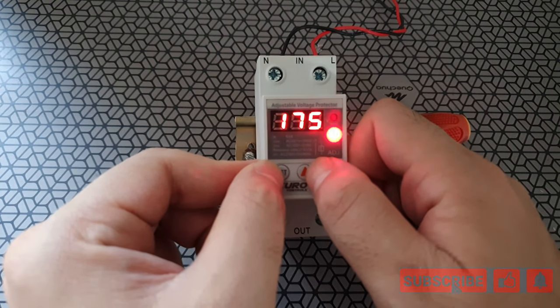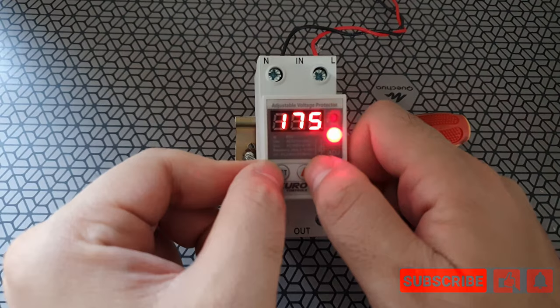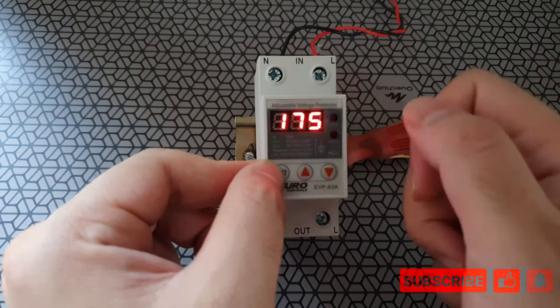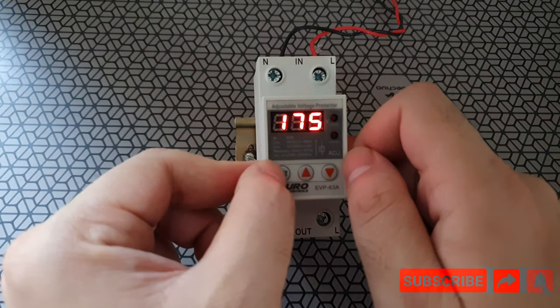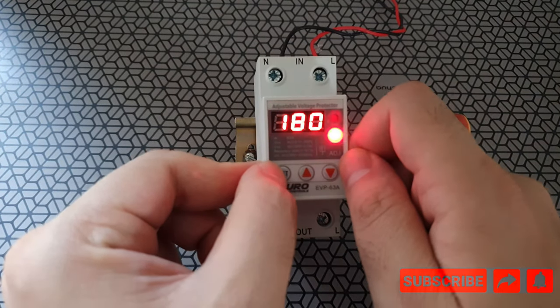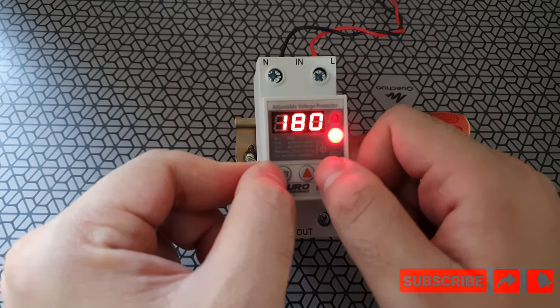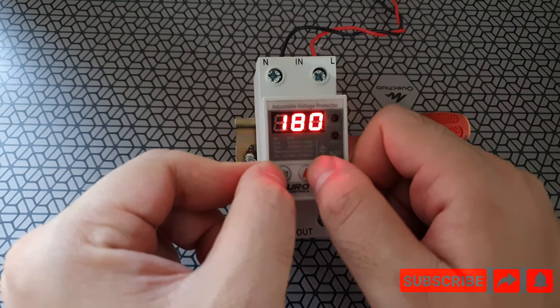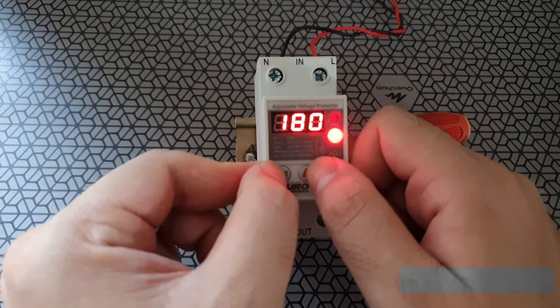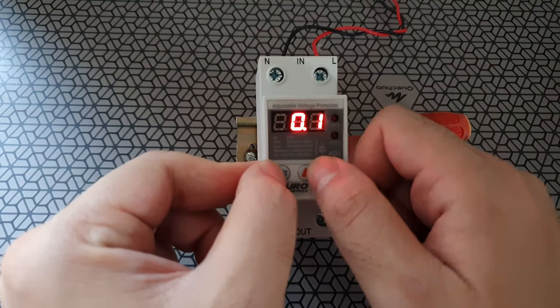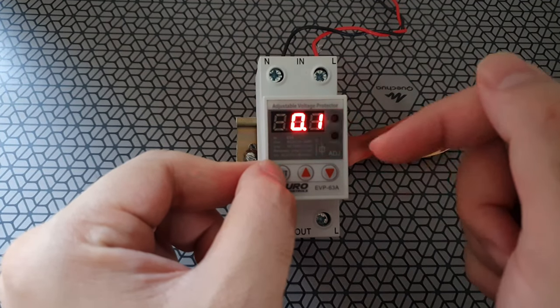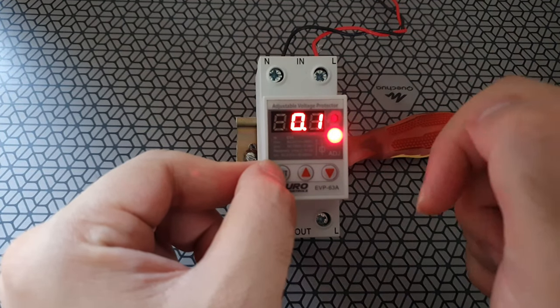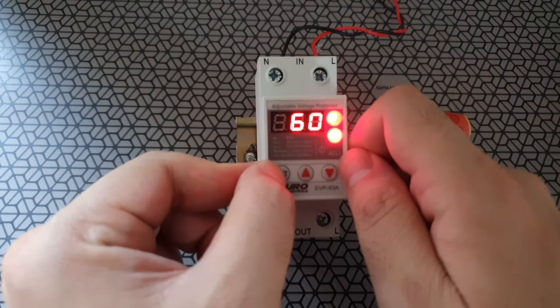So you can set it anywhere between this range. So low voltage will be set at about say 175 volts. I think your devices will be pretty much okay even 175. Low voltage restoration will happen at 180 volts by default. Actuation time, which means 0.1 second response time. It can be adjusted up to 10 seconds if you want to.